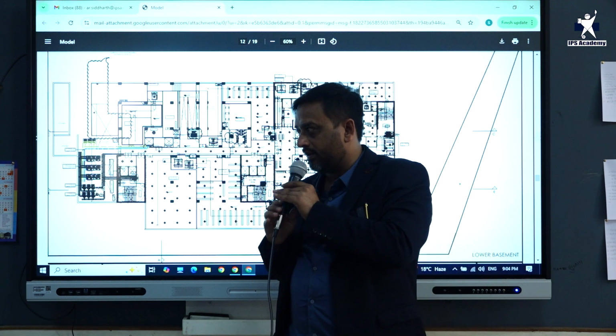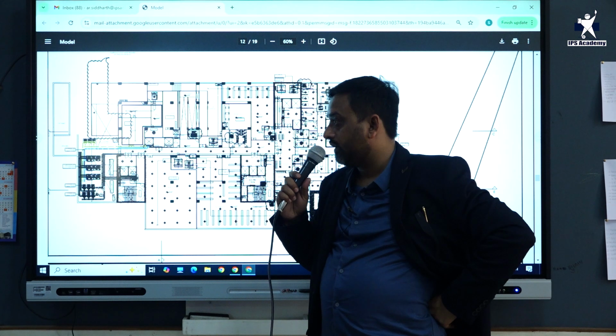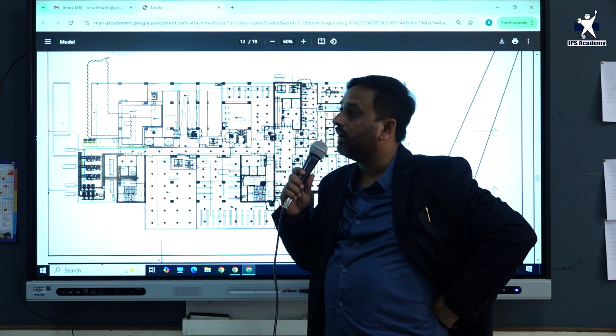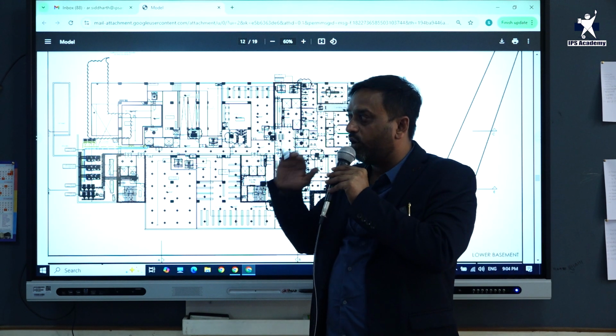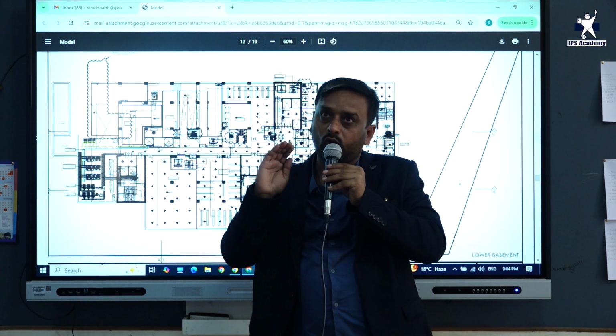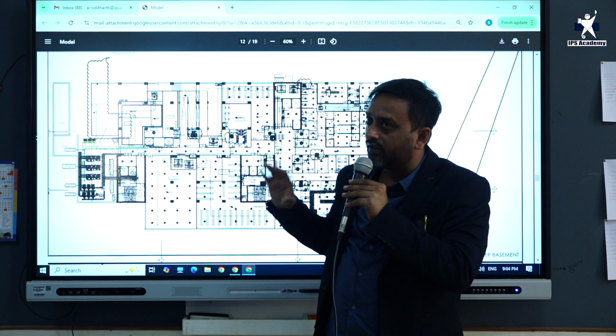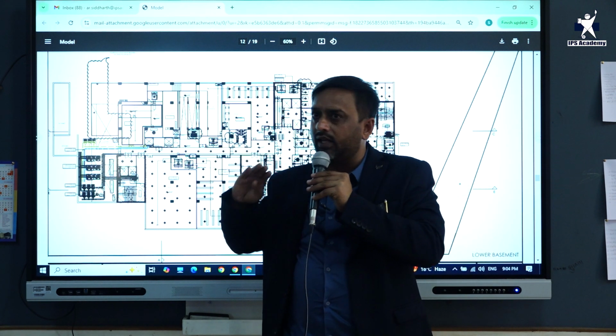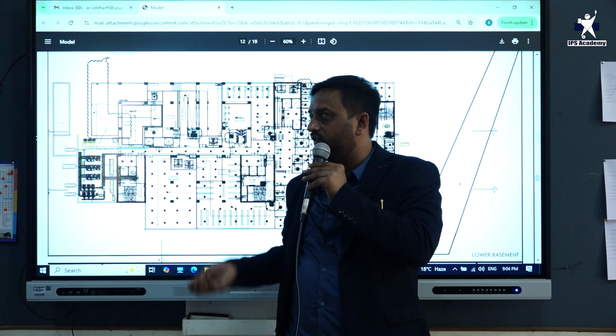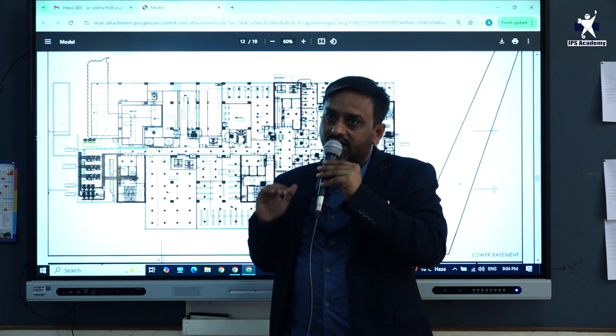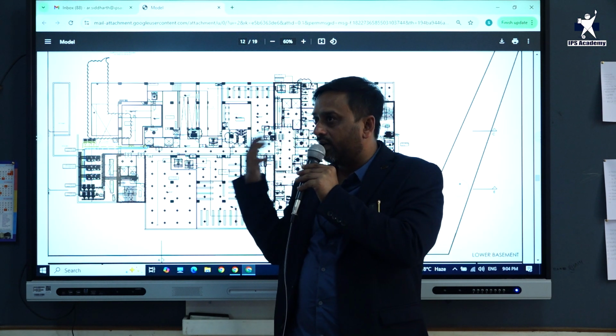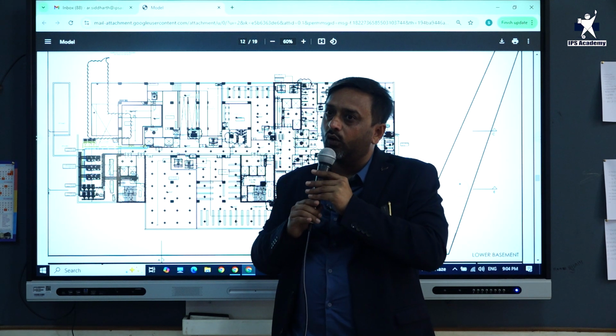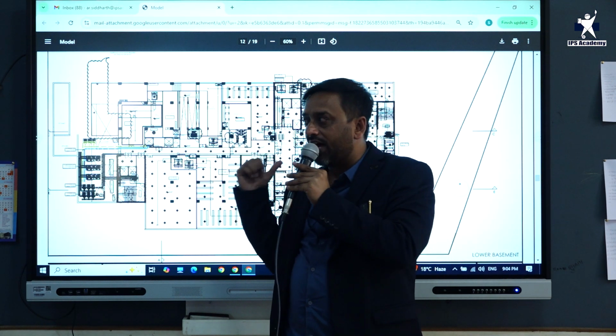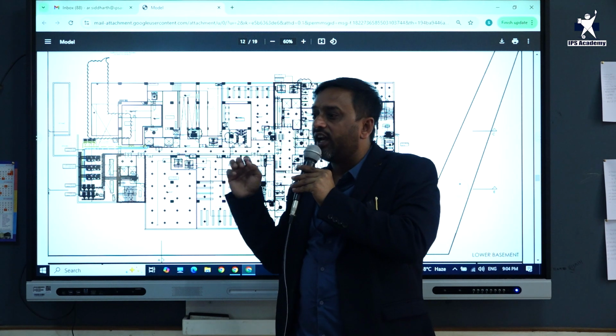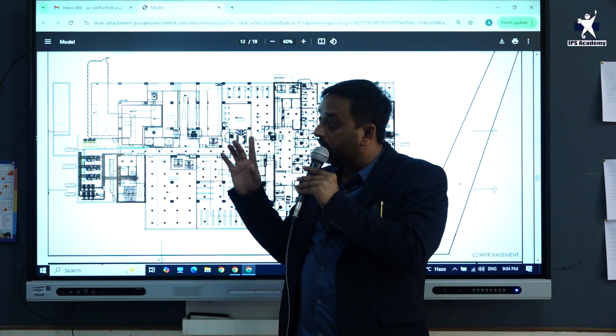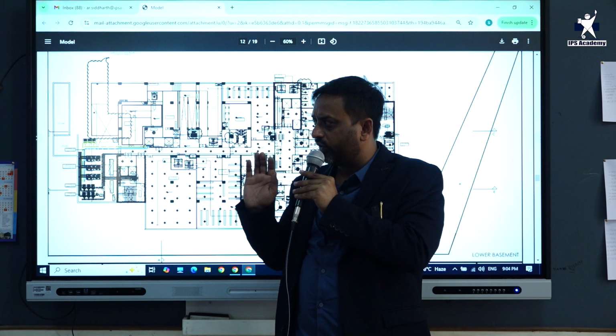You were talking about different kinds of pumps, 5 kinds of pumps. Which pumps? These are monoblock or centrifugal pumps. For our building, in the size and the volume and the height, any pump gets designed on the basis of your height first, then the GPM you need. So when we talk about firefighting pumps, it is 2180 LPM minimum requirement as per laws also.